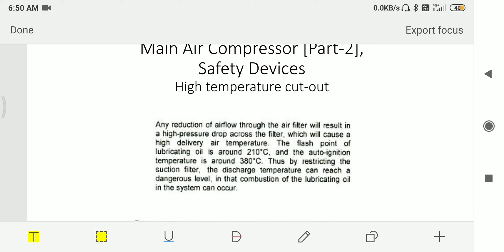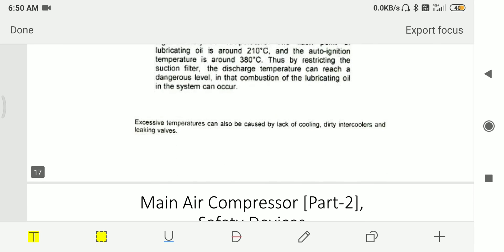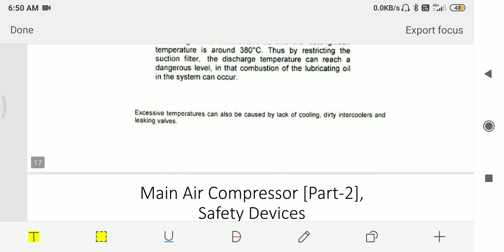Any reduction of air flow through the air filter will result in high pressure drop across the filter, which will cause high delivery air temperature. The flash point of lubricating oil is around 210 degrees Celsius, and auto ignition temperature is at 380 degrees Celsius. Thus by restricting the suction filter, the discharge temperature can reach a dangerous level where combustion of lubricating oil in the system can occur, leading to crankcase explosion. Excessive temperature can also be caused by lack of cooling, dirty intercooler, and leaky valves.